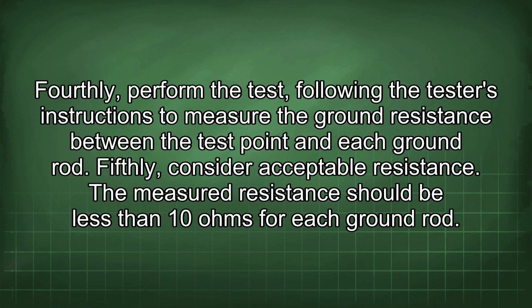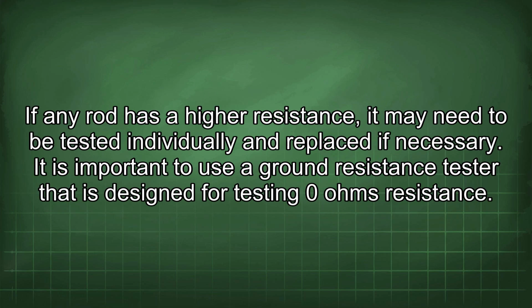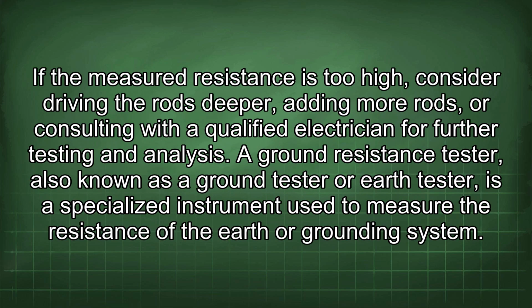Fourthly, perform the test, following the tester's instructions to measure the ground resistance between the test point and each ground rod. Fifthly, consider acceptable resistance. The measured resistance should be less than 10 ohms for each ground rod. If any rod has a higher resistance, it may need to be tested individually and replaced if necessary. It is important to use a ground resistance tester that is designed for testing 0 ohms resistance. If the measured resistance is too high, consider driving the rods deeper, adding more rods, or consulting with a qualified electrician for further testing and analysis.